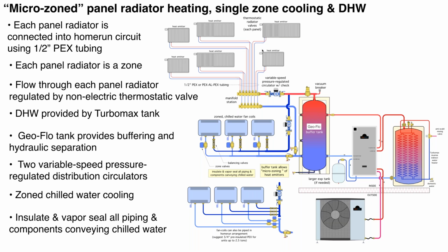So instead of trying to centralize what might ultimately be 8 or 9 tons of cooling, you're using hydronics to go out to what I call satellite air handlers. And then you're clustering short amounts of ducting in those spaces around those air handlers. Now, the other option would be fan coil units. You can get high wall fan coil units. They look virtually identical to a ductless mini split high wall cassette. They're set up with chill water coils and drip pans. You can also get console fan coils, some of which mount to the surface of the wall down low, where the wall comes down to the floor, and some of which can be installed in recessed cavities.